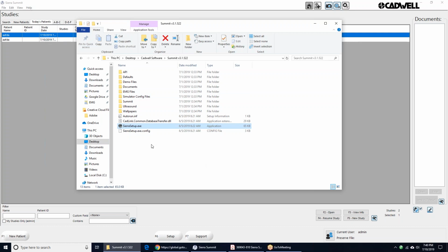So you have the scenario where they're going to use their exact same settings. That is a pretty easy upgrade. It shouldn't take you longer than 10 minutes to do the upgrade and set up a couple things for them. If they want to start using the anatomy database in some of the protocols, that's going to take a little bit more time. Give yourself probably 30 minutes to an hour for the upgrade. And if they're going to be using NCS Plus, and they've used NCV in the past, then plan on some real substantial training on the new software and also setup.